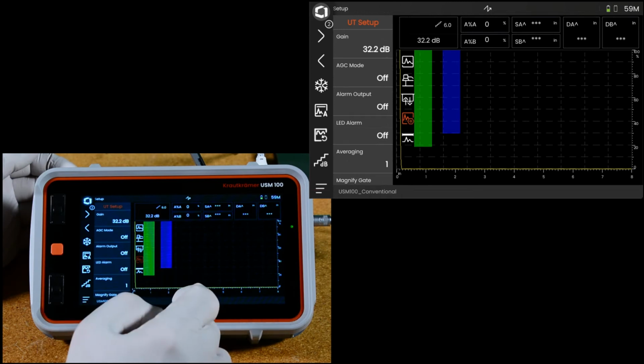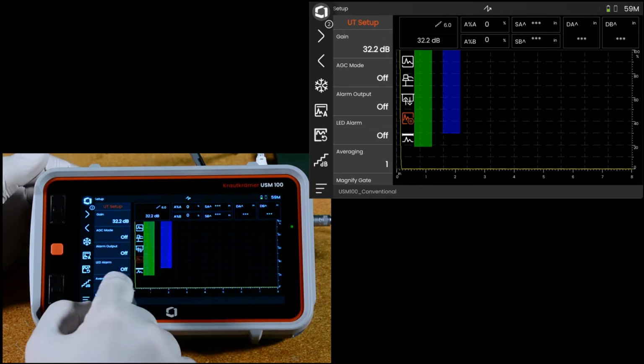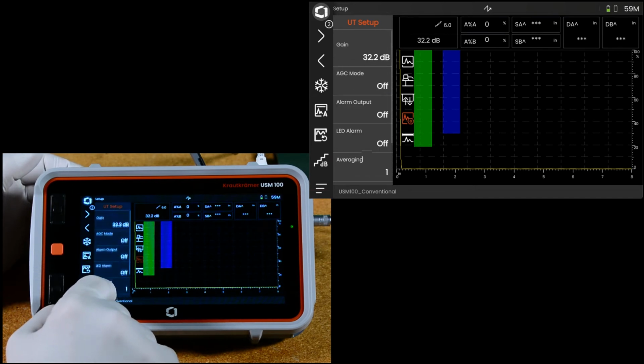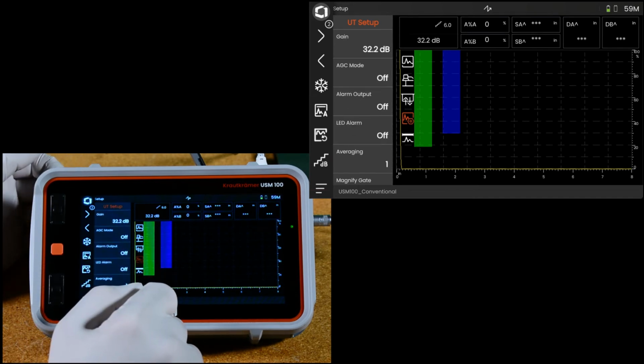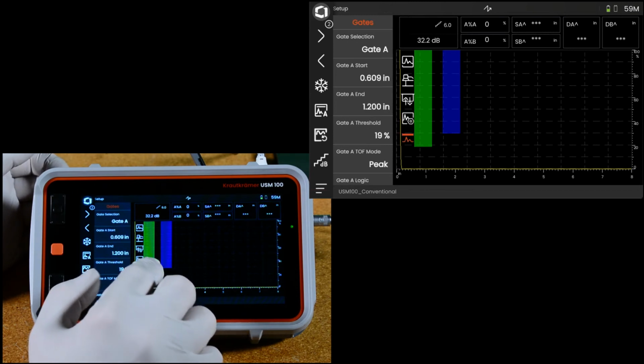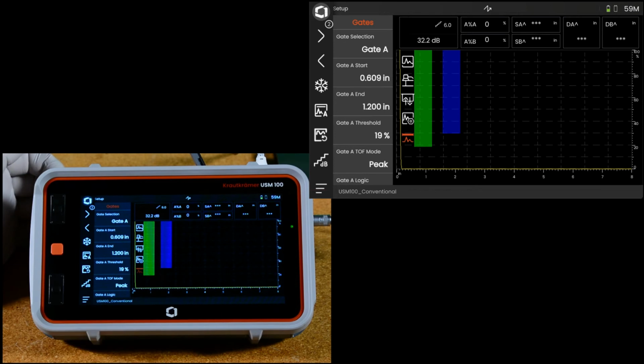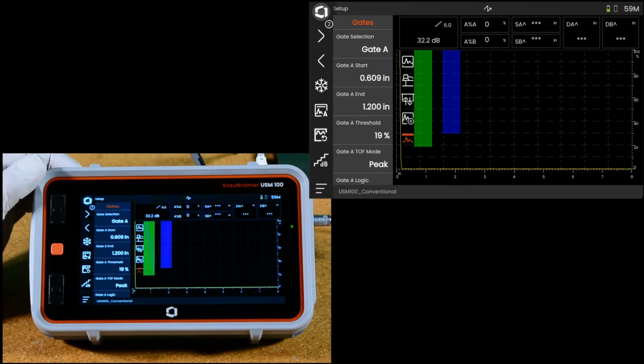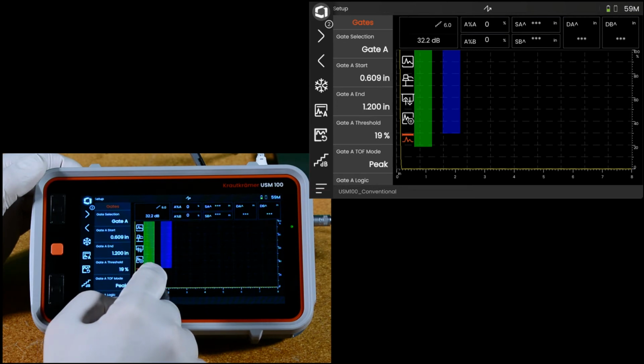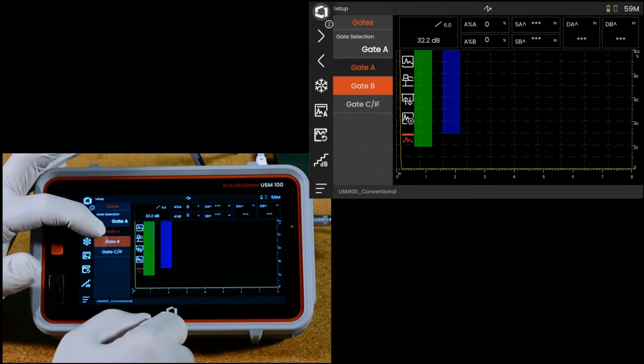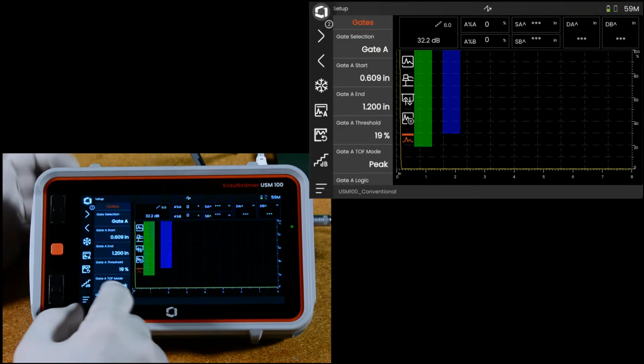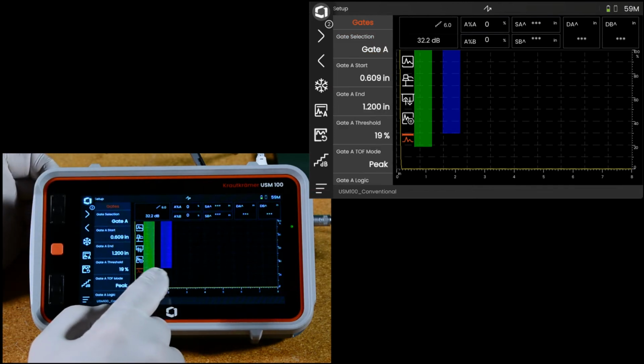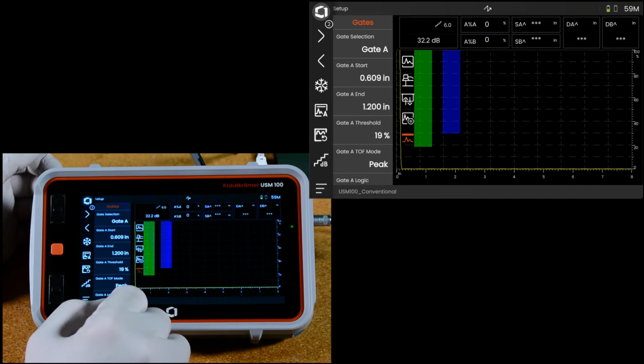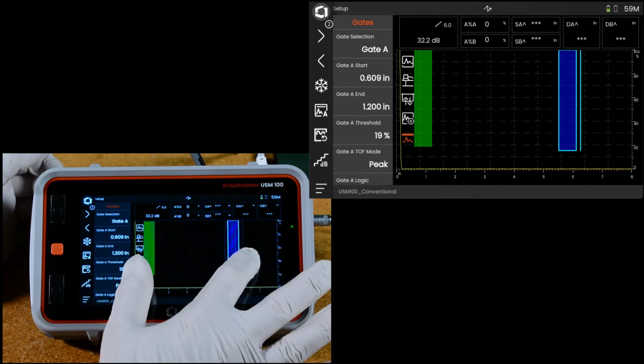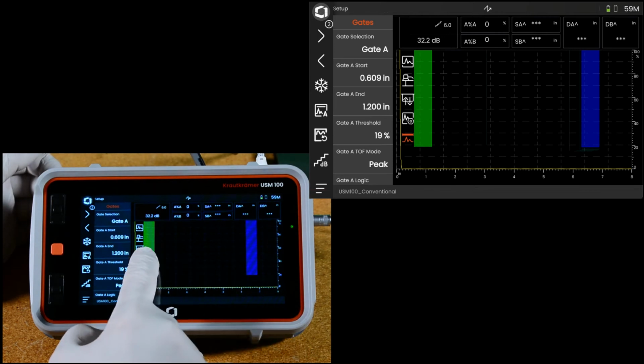Okay. Below that is an A-scan display menu called UT Setup. Here you have lots of controls over your inputs and outputs, things like that. Next menu down is gates. And this menu, again, has some context sensitivity. We have one menu for the gates, and by selecting gate A, B, or C at the top, you get the controls for that particular gate. Now, one thing in the USM 100, because of the touchscreen, it's a lot handier normally to adjust the gate simply by touching on the gate and dragging it around on the screen.